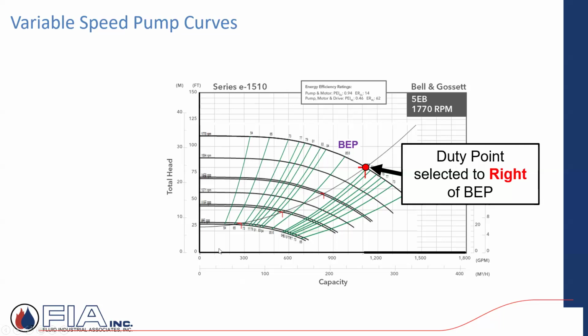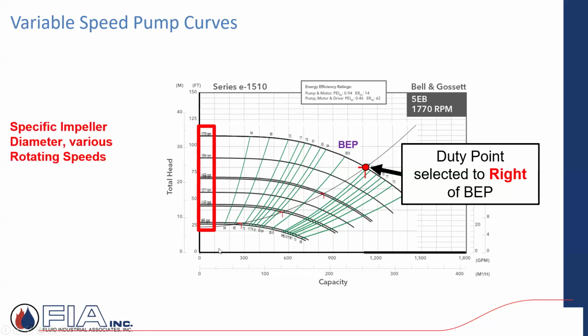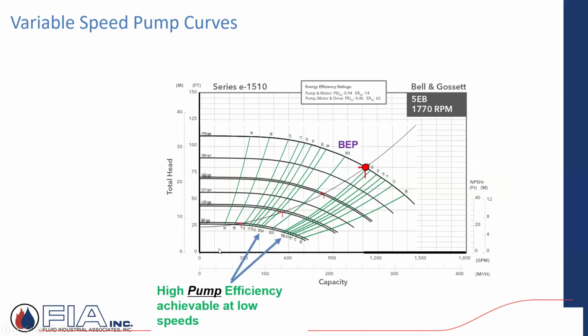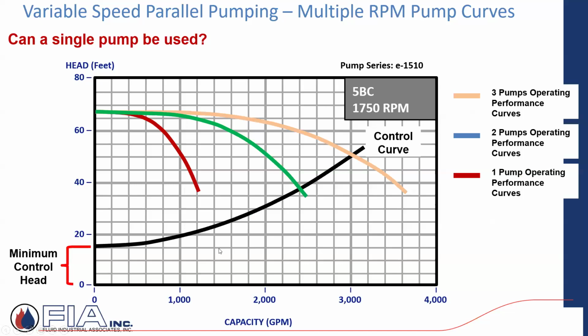Duty point just means what's your design condition, what's your flow and head, what are you calculating? And whatever that is, you might pick it just slightly right of best efficiency point, BEP. And the reason for that in variable speed would be you're going to see a higher percentage of operation. You can still achieve some fairly high pump efficiencies by picking it to the right, because they're not operating out here all the time. They're operating somewhere in this range. So you're still achieving high efficiency with your pump selection, with your pump operation.